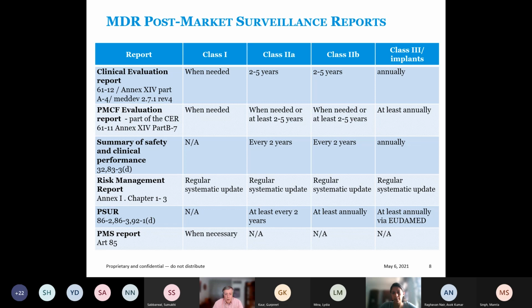What is also interesting, as you can see, is that there is a specific periodicity for each report to be issued, a calendar periodicity. And this periodicity depends on the risk class of the product under the regulation. So if you see, for example, for the clinical evaluation report, for the lower class, which is class 1, it's when needed. For class 3 and implants, it's annually. So you have an increase of the frequency, which is proportionate with the risk class of the device. What is also interesting to note, and which is a further complication, is that when you look inside a specific risk class, look at 2B, for example, you will see that the different reports do not follow the same periodicity, even within one risk class.